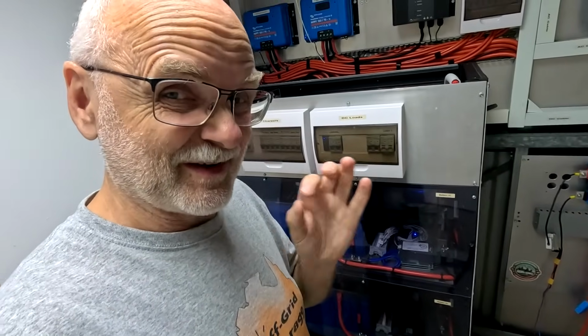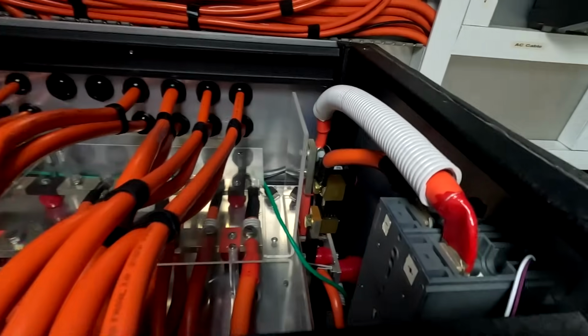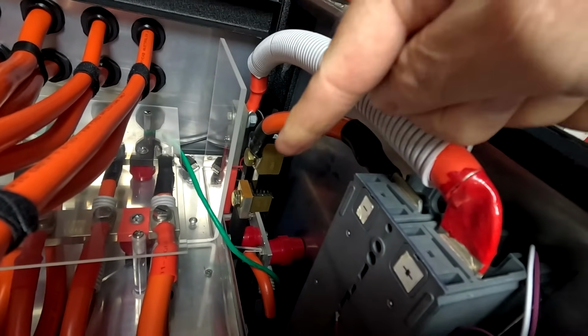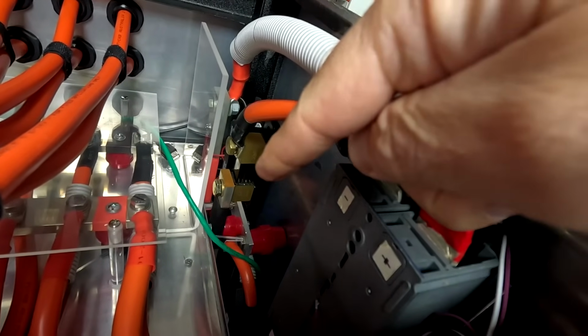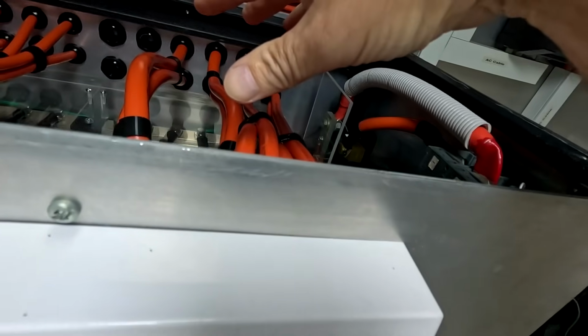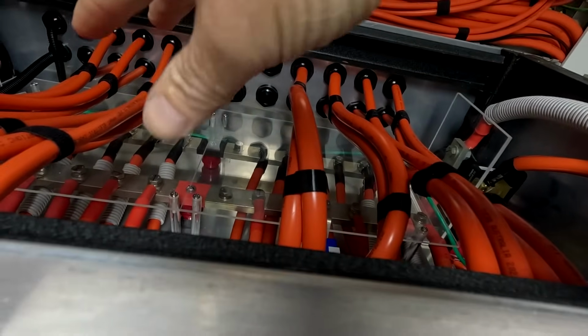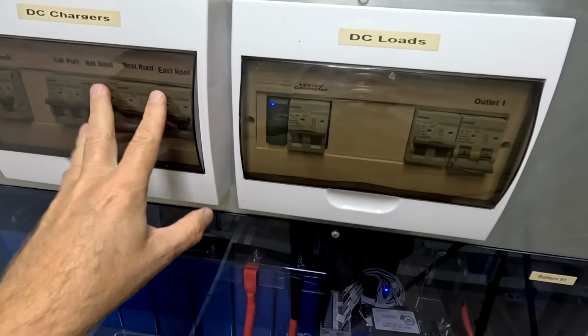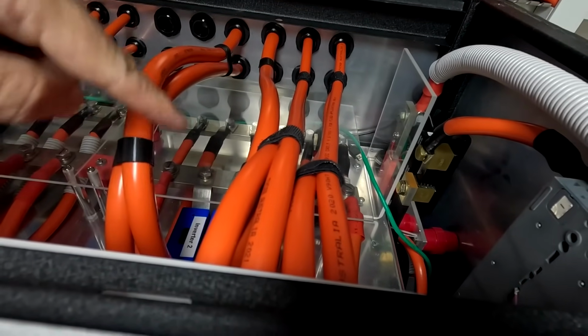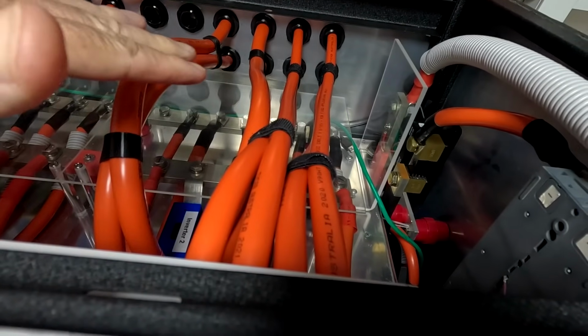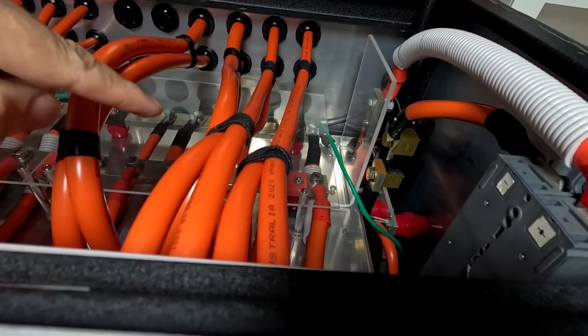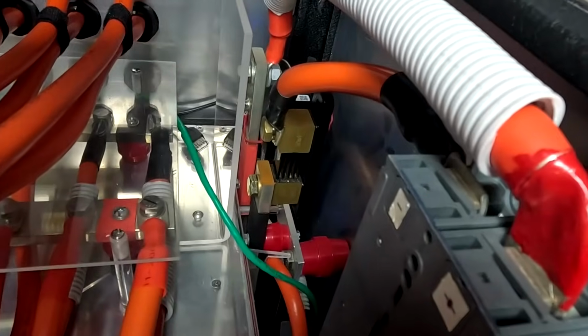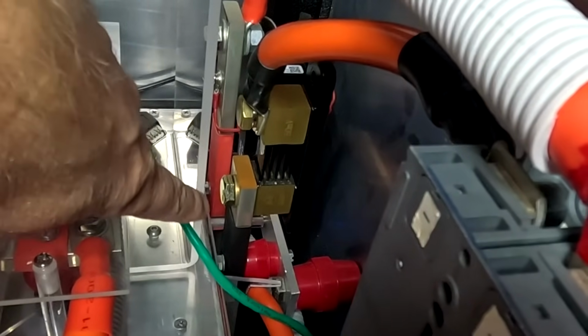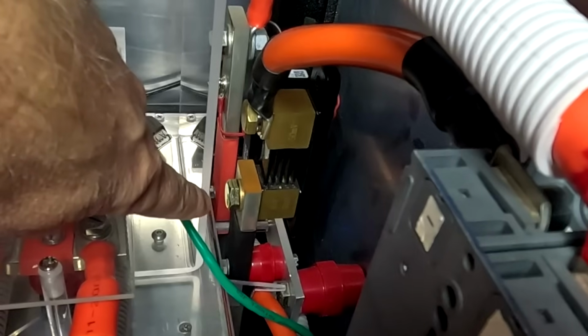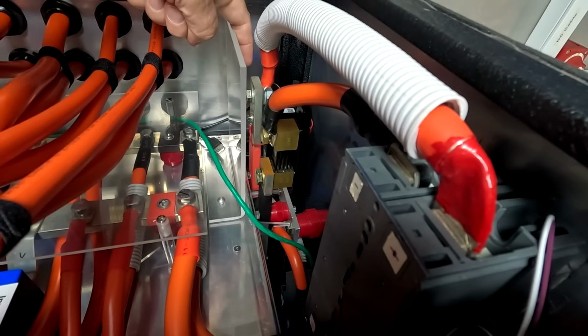So, and then of course there's another challenge. As you know, we've got the Victron Smart Shunt in here. There it is, you can see it over there. That's the Smart Shunt, which basically separates our batteries from the rest of the system. Yeah, all the chargers and loads are connected to these two bus bars up here, and we can isolate them with these circuit breakers in the front. I cannot connect any additional batteries just to these bus bars here. Technically it would just work fine, but we are not measuring the energy going into these additional batteries. So we would need to connect these additional batteries at the lower side of this Smart Shunt, down there, and on the other side here for the positive as well.